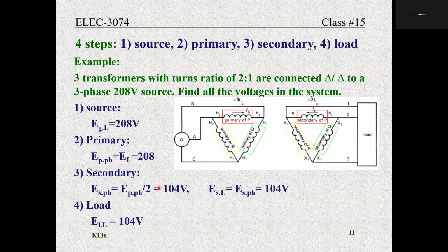On the secondary, first we have to find out what this voltage is. We know what this one is — 208 — and we know the ratio is 2 to 1, twice as many windings here than here. So this voltage is going to be half of what is here: 208 divided by 2 gives us 104 volts. So we know the phase voltage is 104.